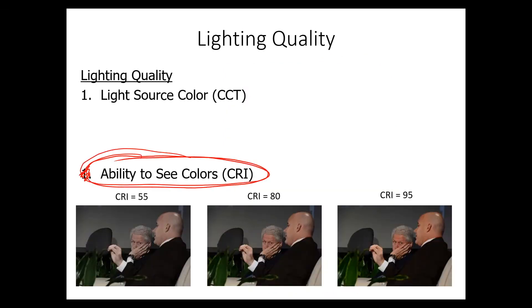Now let's talk about color rendering index — your ability to distinguish colors. The color rendering index goes from a scale of 0 to 100. It was established based on the incandescent lamp for interior lighting, so 100 is not the absolute best; outdoor lighting under bright sun conditions would be better than that. At a color rendering index of 55, the picture looks just kind of gray. As you get closer to 100, you're getting more reds, and really close to 100, you can really see the reds, hues, and face tones.